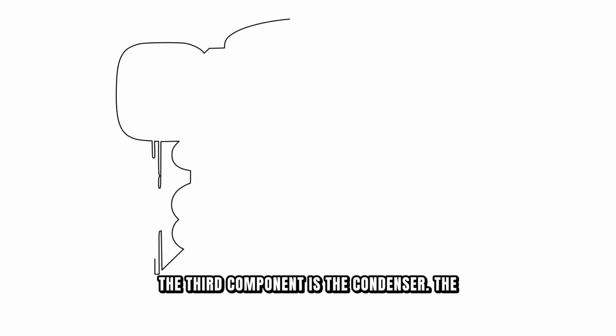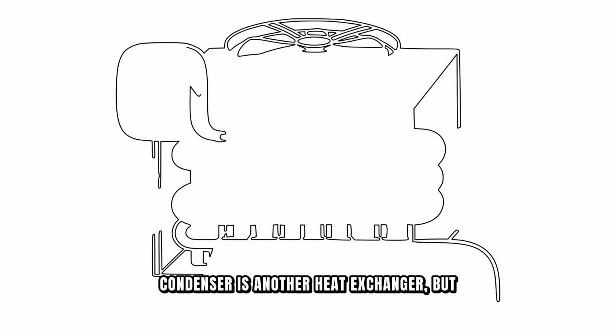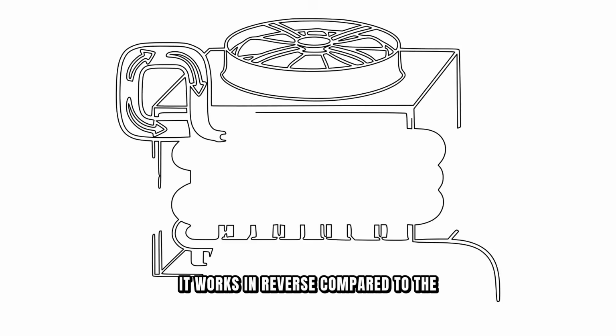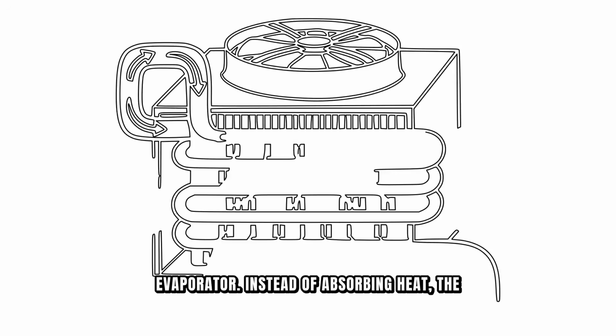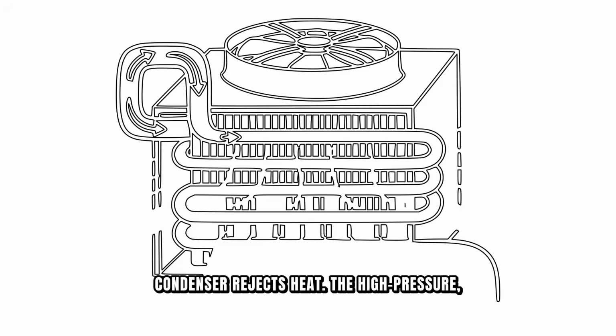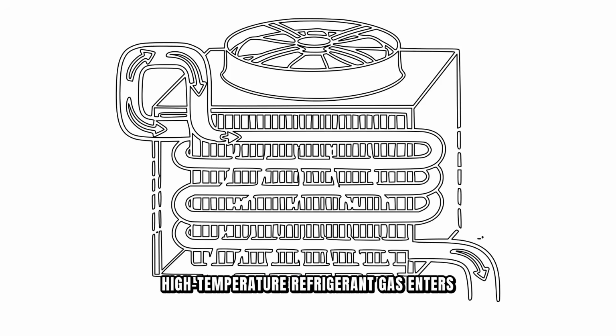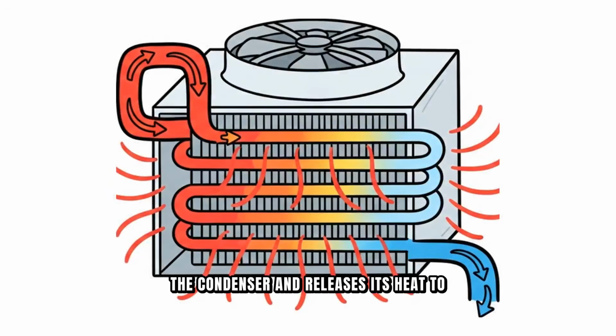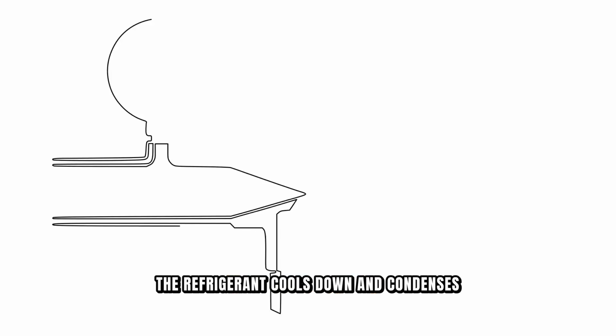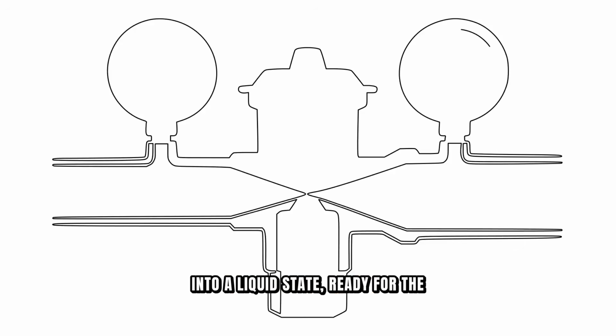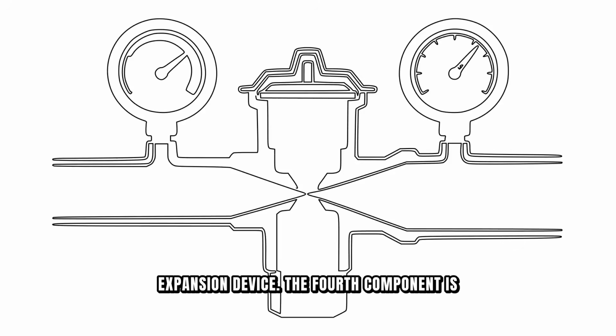The third component is the condenser. The condenser is another heat exchanger, but it works in reverse compared to the evaporator. Instead of absorbing heat, the condenser rejects heat. The high-pressure, high-temperature refrigerant gas enters the condenser and releases its heat to either outside air or to water, depending on whether it's an air-cooled or water-cooled chiller. The refrigerant cools down and condenses into a liquid state, ready for the expansion device.